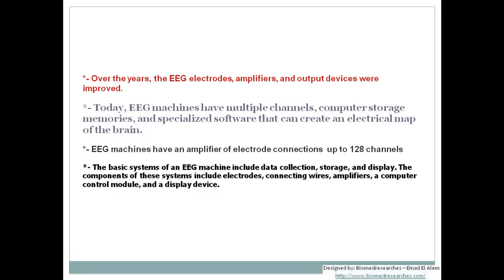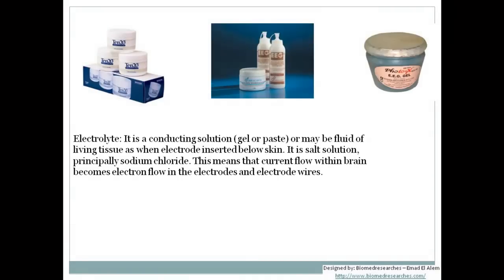The basic systems of an EEG machine include data collection, storage, and display. The components include electrodes, connecting wires, amplifiers, computer control module, and a display device. A key component for starting an EEG test is the electrolyte — a conducting solution, either gel or paste, or a fluid of living tissues when electrodes are inserted below the skin, which is principally a salt solution such as sodium chloride.